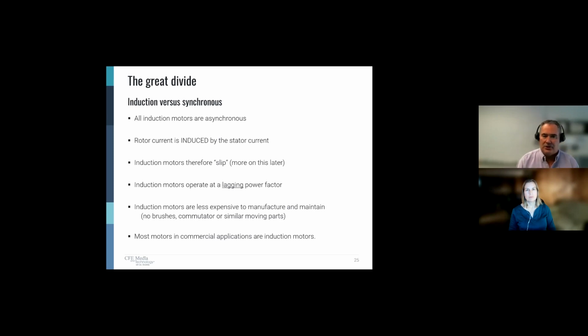But even within that space, there's another divide, and that's induction motors versus synchronous motors. All induction motors, which is what Tesla invented and what we're most familiar with, are considered asynchronous. What that means is the rotor current is induced by the stator current, hence the name induction motor. But because of that, these motors will slip, or they have a component called slip, and we'll talk about that a little bit more later. Additionally, because of that slip, and because of the way these motors run, they operate at a lagging power factor. Everyone remembers power factor, and we'll talk about that a little bit more. The power factor, for the most part, is okay, but it can be our enemy. And again, we'll talk about that here in a few minutes.